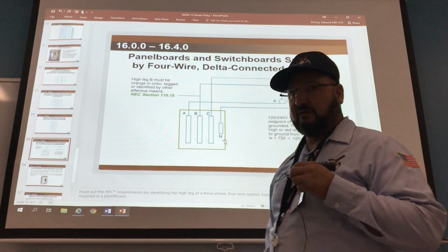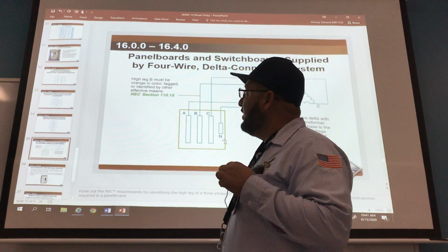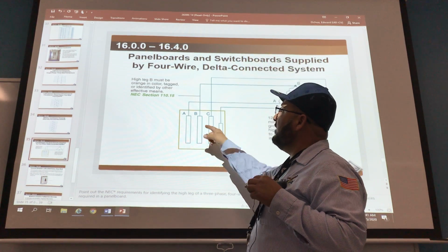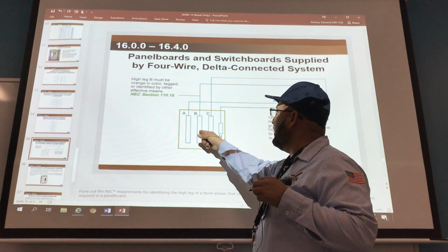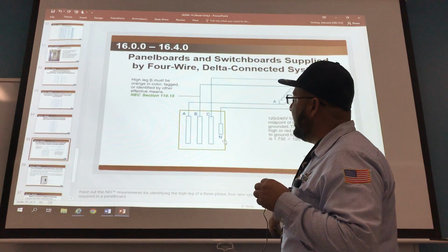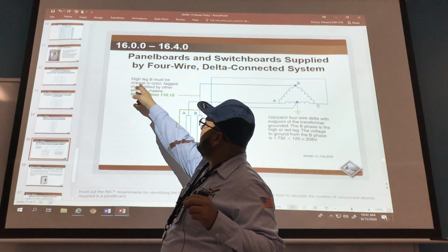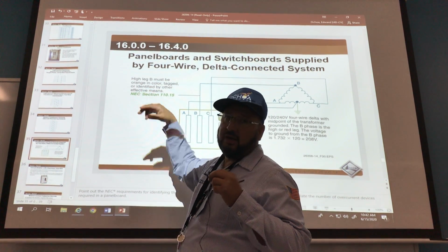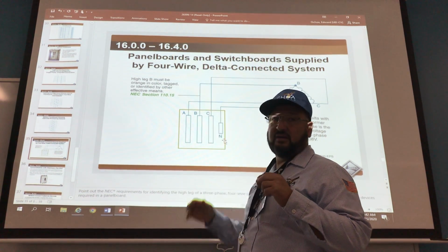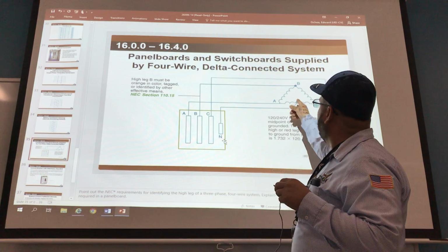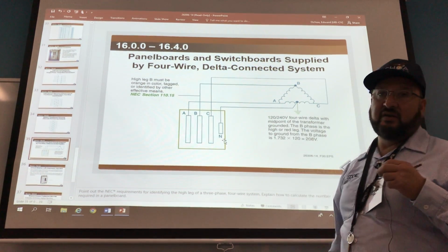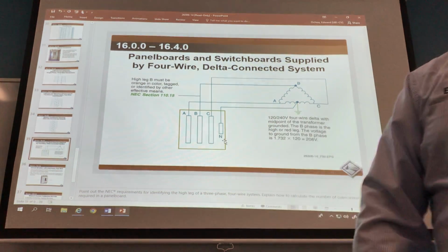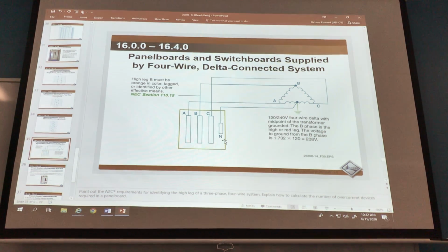I sent you guys a video from when I worked at Chipotle, and this is what they had. They had the high leg in there, and it was marked. It was tagged. And this says it should be tagged orange. The one I had was tagged yellow because they had it on the C phase. But normally your high leg is on the B phase. So I'm not too sure why that is different from what I saw and what this is.